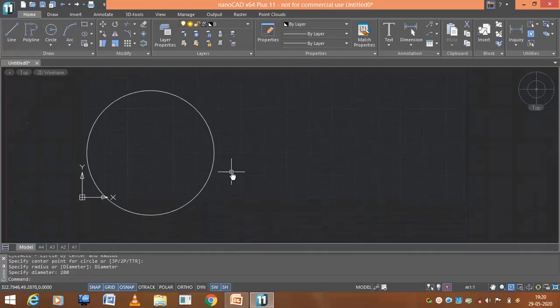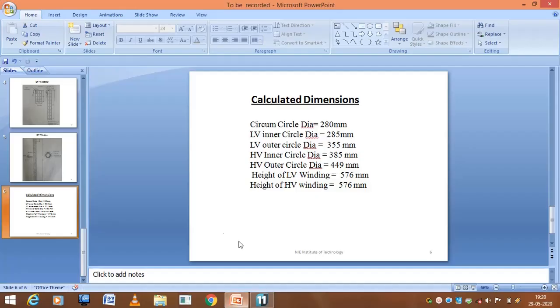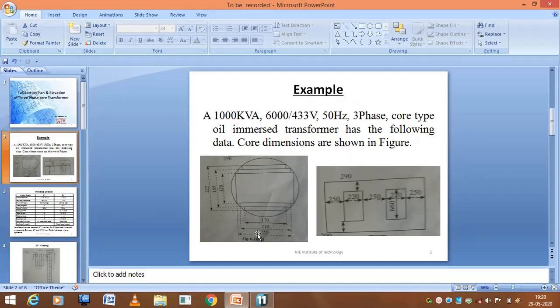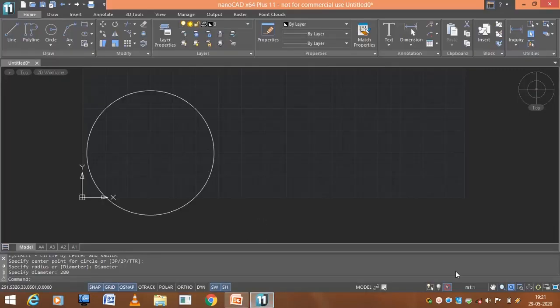and it is a three step, right? It is a three step, it is given here. It is a three step, and the step details are also given. And here you can notice one thing: the step horizontally and then vertically it is different, it is not equal. Horizontally, if the largest step is 250, vertically it will be 222. It means there will be a slight variation in the drawing procedure to draw this three step core. So let me concentrate on the horizontal steps, that is 250, 210 and then 170.